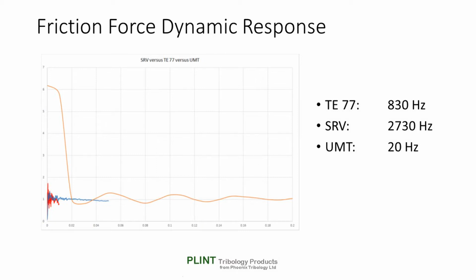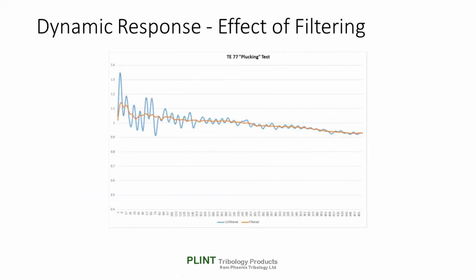Repeating the plucking test with a UMT machine, we see that it has a much lower signal bandwidth than either the TE 77 or the SRV. This is because the device has a relatively high mass specimen assembly cantilevered off a relatively low stiffness force transducer. Providing we have high enough signal bandwidth, we can of course tidy up our friction signal with a suitable filter. In this example we have used a filter that removes the resonance, but we have to bear in mind that it will also remove any true friction effects at the same frequency.